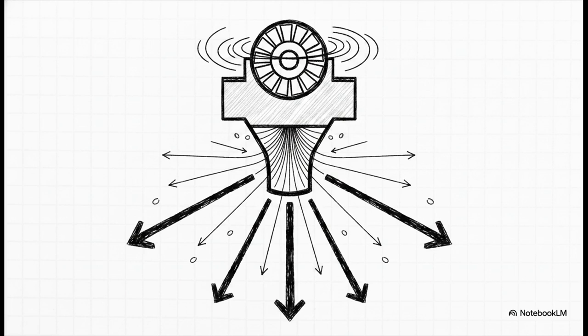But the brilliant engineering doesn't just stop once the turbine is spinning. After the water violently turns the turbine, it enters what's called the draft tube. This is a specially shaped diffuser that serves a super vital role by recovering kinetic energy. It actually converts the remaining velocity of the water back into pressure head, which maximizes the turbine's efficiency right before the water is finally discharged.